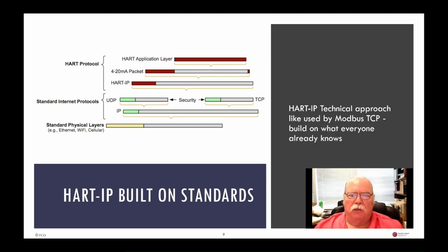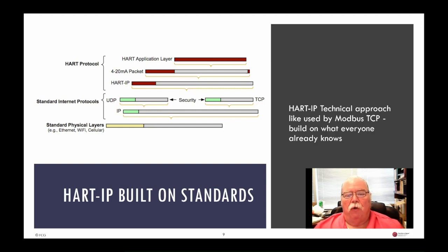HART-IP works just fine over cell phones, packet radios, Ethernet, Wi-Fi, satellite — it doesn't care about the physical layer. We took a very similar approach to Modbus TCP: build upon what people already know, which is the HART protocol. We put a very thin wrapper called HART IP around standard HART commands and standard HART packets. That means all systems that know HART can use HART IP with minimal modifications.